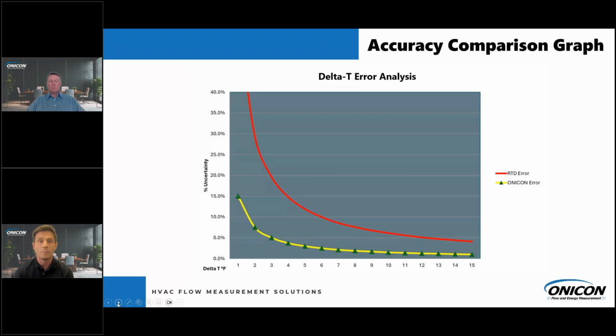And as we know, not every system is perfect. You don't always have a true 10-degree delta T across systems such as a chiller system. Sometimes it's 7, 8. And as you see that delta decrease, your error increases.